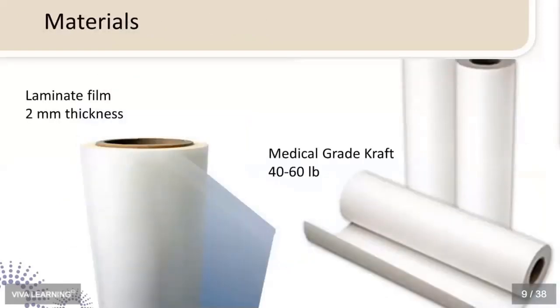Some things you should know when you're selecting, in particular, pouches at this point. Pouches are basically made up of paper, laminate, and adhesive. So just looking at a pouch, you don't know about the quality of the materials. Some of the questions you might want to ask are what type of paper is used to create that pouch? You're looking for words like medical grade or surgical grade and kraft paper, kraft with a K. This type of material is a pure cellulose material. There are no other byproducts put into that paper as filler, so it's going to be consistent across the entire grain of the paper, which allows the penetration of the steam very evenly.